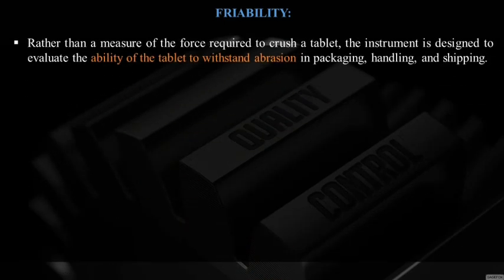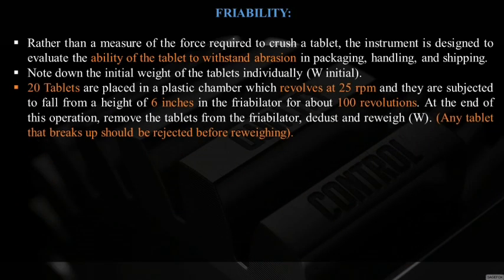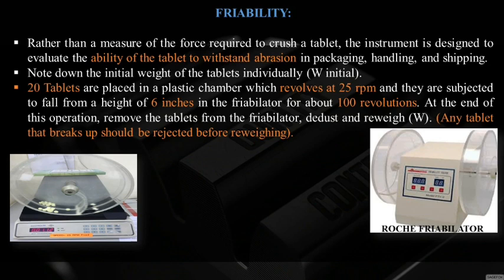Rather than measuring the force required to crush a tablet like a hardness tester, the friabilator is designed to evaluate the ability of the tablet to withstand abrasion during packaging, handling, and shipping. Note the initial weight of 20 tablets (W-initial). The 20 tablets are placed in a plastic chamber — the Roche friabilator — which revolves at 25 rpm, subjecting tablets to falling from a height of 6 inches for about 100 revolutions, running for 4 minutes.